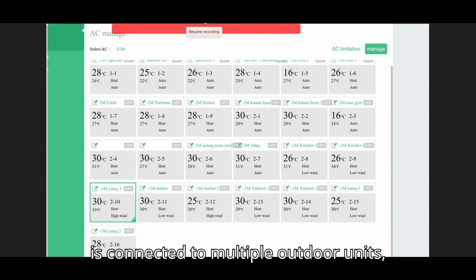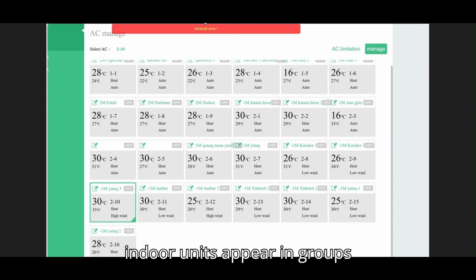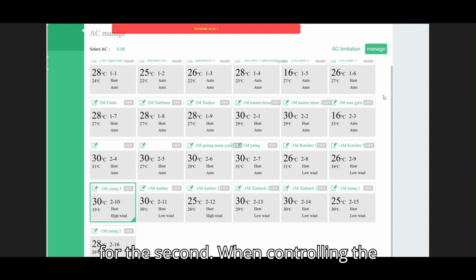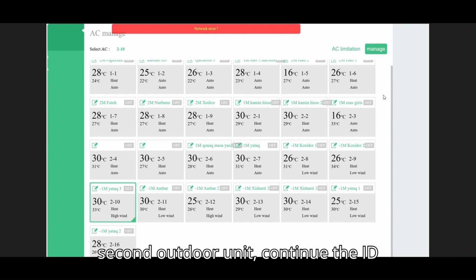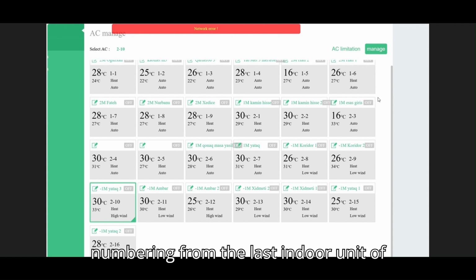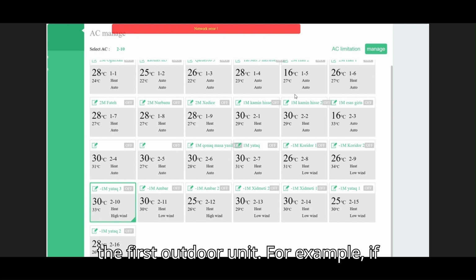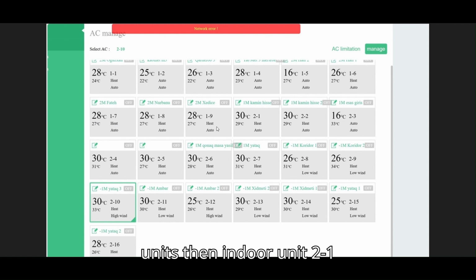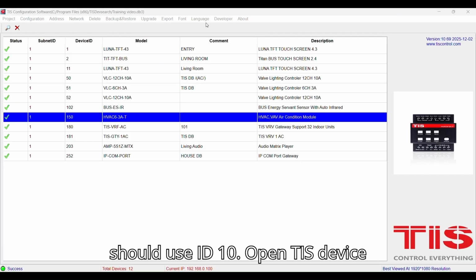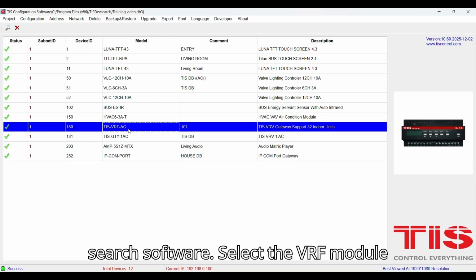If the module is connected to multiple outdoor units, indoor units appear in groups: 1 to 1, 1 to 2, 1 to 3 for the first outdoor unit, and 2 to 1, 2 to 2, 2 to 3 for the second. When controlling the second outdoor unit, continue the ID numbering from the last indoor unit of the first outdoor unit. For example, if the first outdoor unit has 9 indoor units, then indoor unit 2 to 1 should use ID 10.